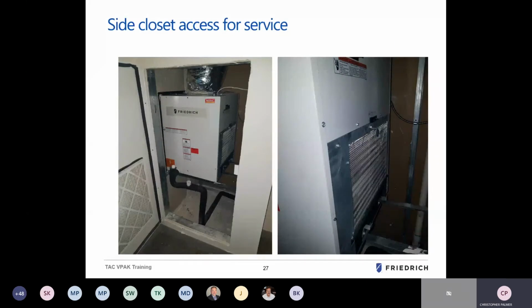This one here is another left-hand installation, drain line coming off underneath, unit mounted on the unistrut system that they constructed, and then the access panel here. If you notice here, the Friedrich access panel has this black gasket. That gasket material, when closed against the drywall, creates an airtight seal, so the air infiltration to the closet is through the filter.